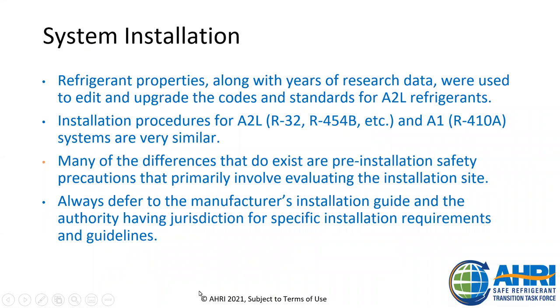I'm going to speak a little bit about system installation as it pertains to the new refrigerants, the A2Ls, the low GWPs. Refrigerant properties, along with years of research data, were used to edit and upgrade the codes and standards for these A2L refrigerants. Many of the safe work practices employed with A1 refrigerants are still relevant when we're working with the A2Ls. Many of the differences that do exist are pre-installation safety precautions that primarily involve evaluating the installation site. The two golden rules to remember are to always defer to the manufacturer's installation guide and the authority having jurisdiction for the specific installation requirements and guidelines.